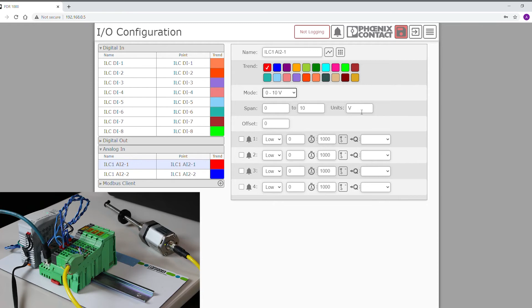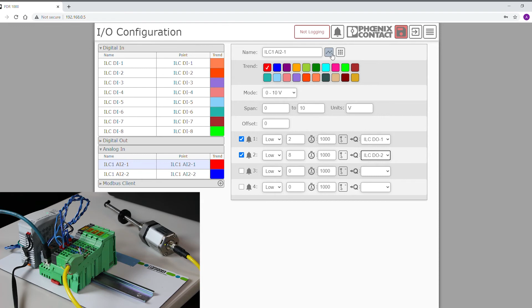There are a few other options we can go in and set up. In our case, we're going to set this up like a high, go, low: our low output, whenever we hit 2 volts and get below that, we want to set up an output, and whenever we get above 8 volts, we want to set up an output. We can then set up the time before that alarm goes out, and define what kind of output—what we want to happen when we hit that alarm state. In our case, we're just going to signal a couple of discrete outputs, maybe a local alarm that could go out to a stack light.